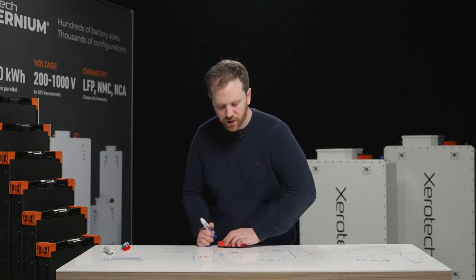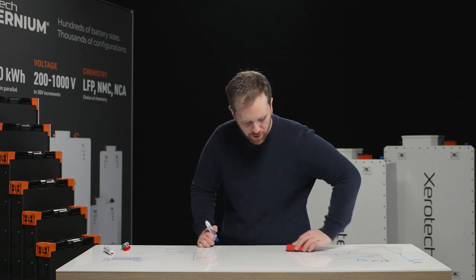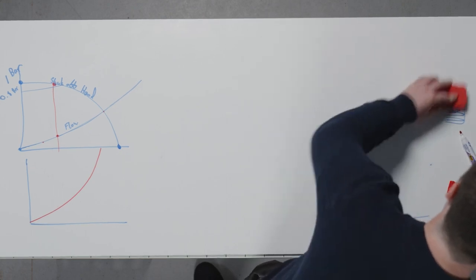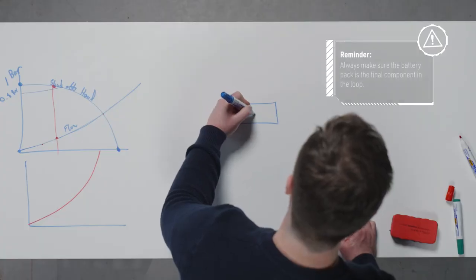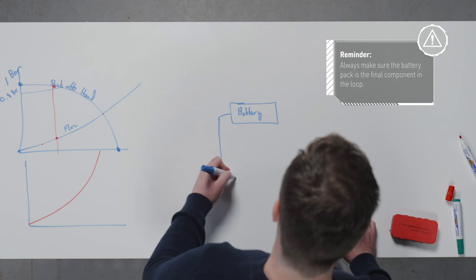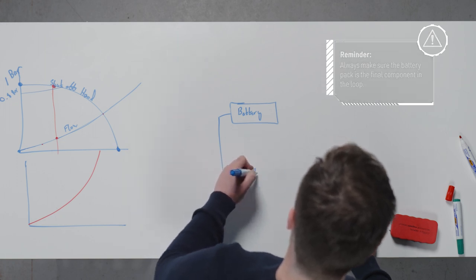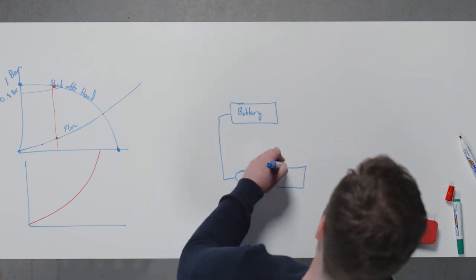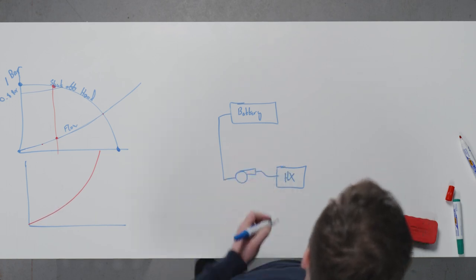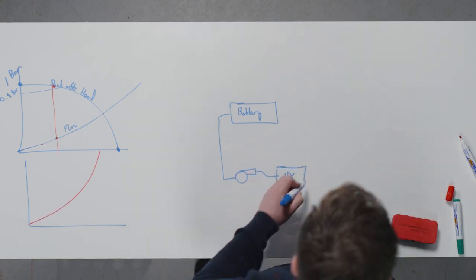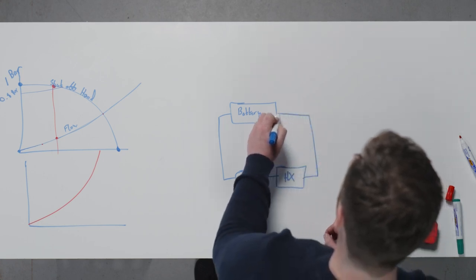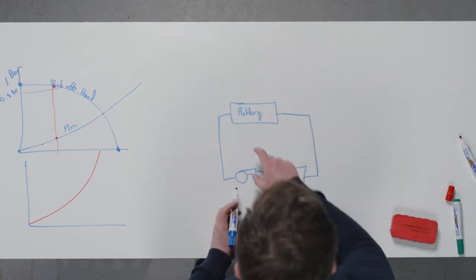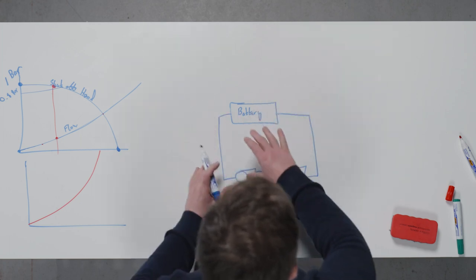The other piece for a standard system to best optimize it is to make sure all of the relevant components are in the right locations. So the ideal plumbing system configuration for a Xerotech battery is you have the battery as the final component before the pump, goes back into the pump. Your pump goes through your plate heat exchanger or whatever form of heat exchanger you're using to put heat in or out of the battery, and then it goes onwards to the battery. So you will see the battery has the minimum pressure as it's the last component.